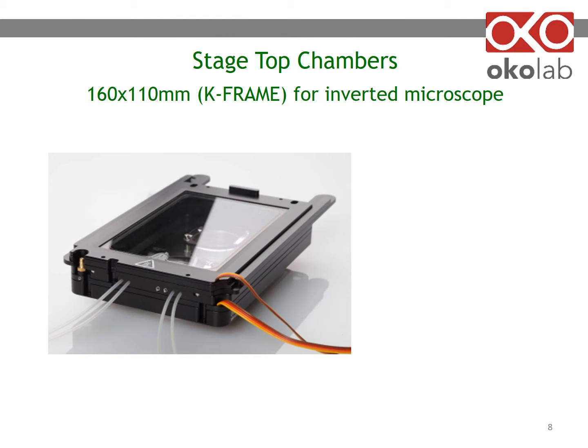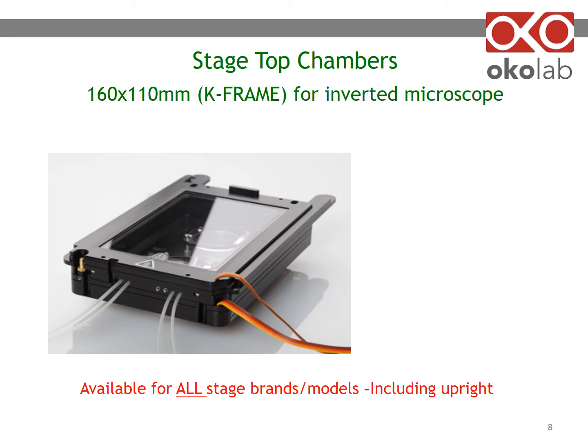To illustrate the microenvironmental chambers, I will use a K-frame for inverted microscopes. A K-frame simply fits a microscope stage with an opening of 160 by 110 mm. This is just an example, as chambers for all stage brands and models, including upright, are available. OkoLab K-frame chambers have built-in perfusion holes — they come plugged with small screws, and you can unplug them if you need to do perfusion.